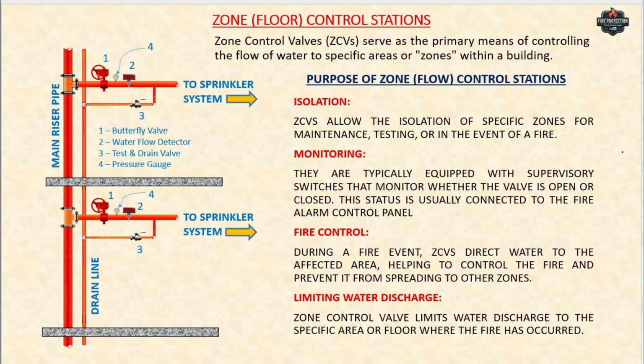Now let us see what is the purpose of these zone control valves. The zone control valves allow specific areas or floors of the building to be isolated from the rest of the sprinkler system. This helps in maintenance, repairs or modification in one area without shutting down the entire fire protection system. Suppose this valve is not here, and you want to repair something in this area, then you have to close the main valve which is near the fire pump. But if the valve is there, you just close this valve and you can do maintenance here and then open the valve.